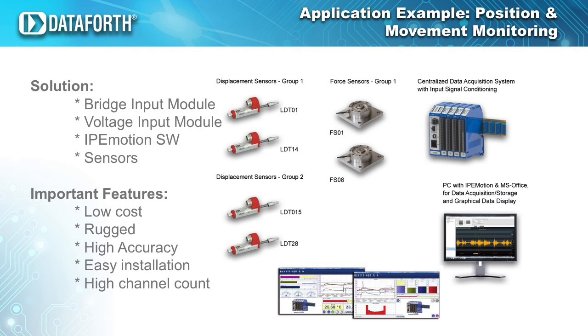However, general contractors usually have other specializations than developing and installing data acquisition systems. Therefore, the contractor, with help from a local engineering firm, developed this plan to install sensors and a data acquisition system for monitoring any movements of the building during construction. The monitoring system they developed is comprised of 28 displacement sensors and 8 force sensors mounted on hydraulic actuators, which are connected to a MAQ20 data acquisition system located near the point of measurement. A networked general-purpose computer runs IPE-Motion data acquisition software with a specialized plugin to interface to MAQ20 hardware.